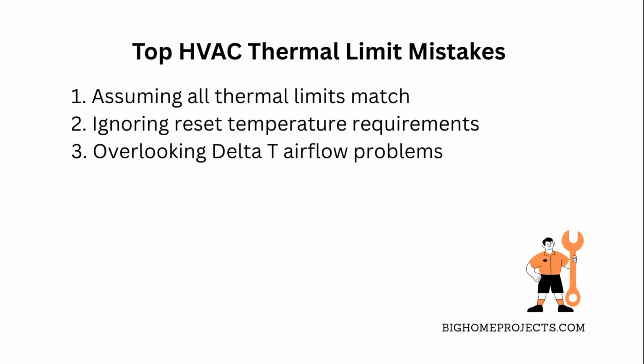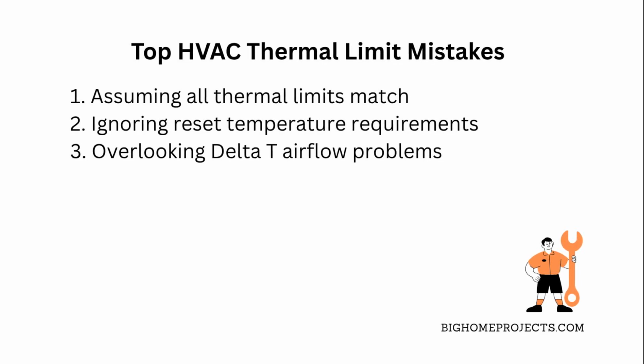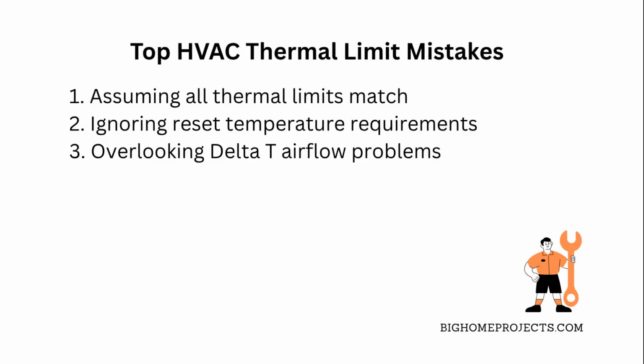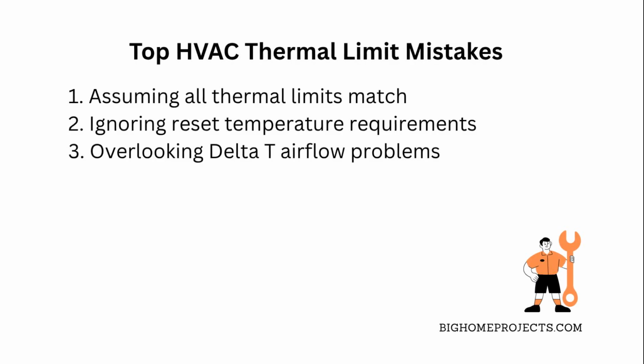Fix these by always verifying the exact thermal limit temperature rating for your specific equipment, understanding the reset temperature to know when the system should come back online, and checking your Delta T regularly as part of routine maintenance to catch airflow or heat exchanger problems early.